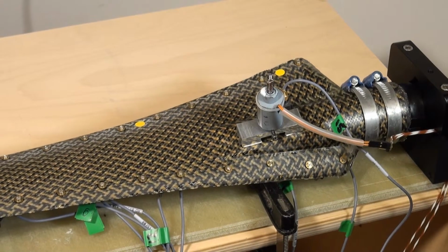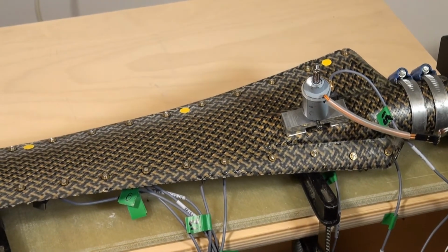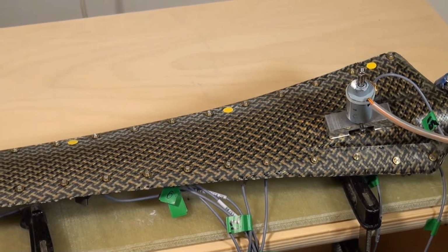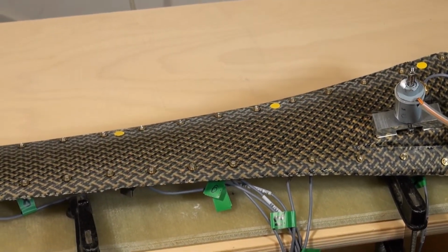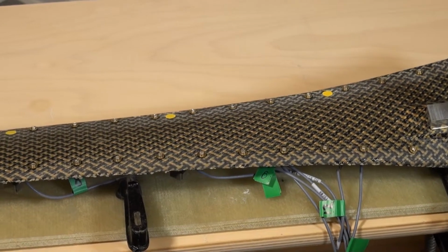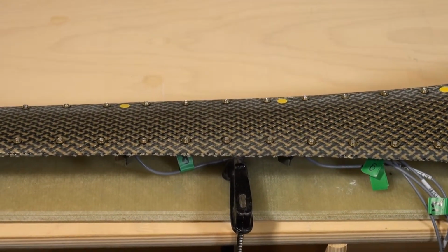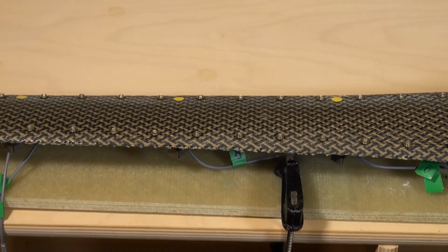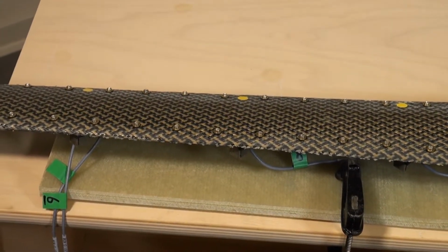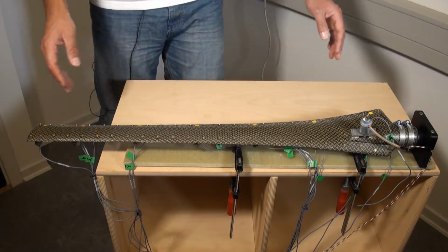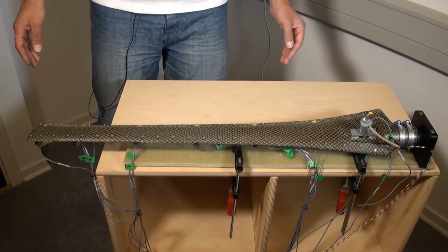First, we need to collect statistics about the reference state. For that, we will start the actuator, and it will do around 100 hits. During these hits, the signals from the accelerometers are measured, and based on these signals, we make a model of the undamaged reference state. Now all the bolts are tightened, and all I need is to start the actuator.